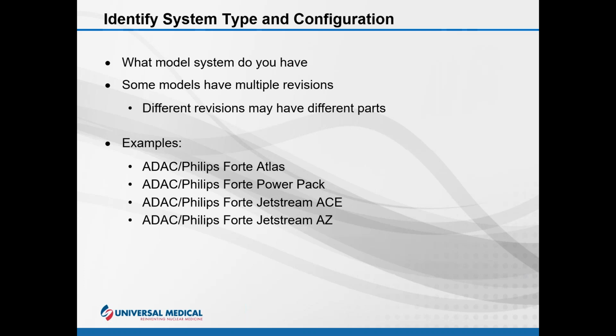The detector card rack was replaced with the Meritage motherboard. This change led to redesigned detector bonnets on the outside. And like before, the change of detector types also required several other internal changes to power supplies and electrical components. Also, the patient table was redesigned. So as you can see from this one example, it is extremely important to know the exact make and model of your system when asking for assistance.